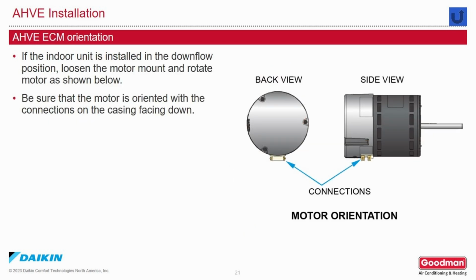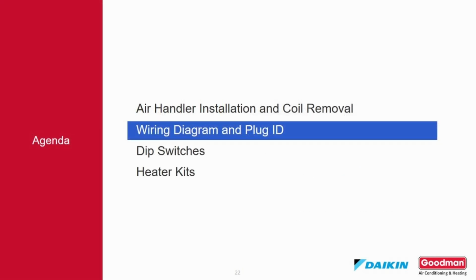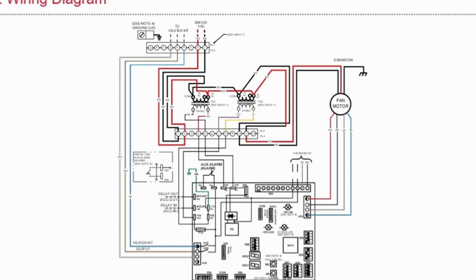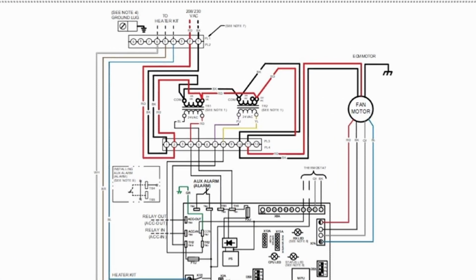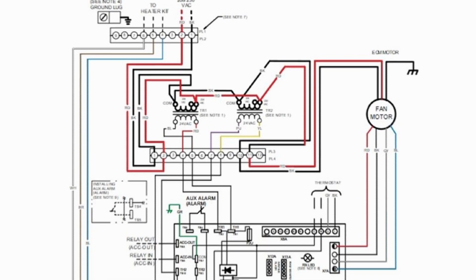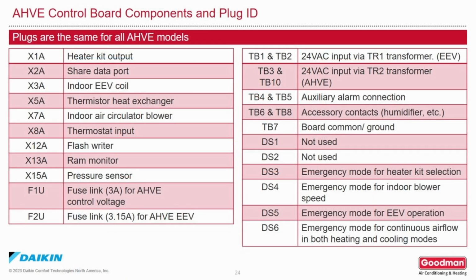AHVE ECM motor orientation. If the indoor unit is installed in a downflow position, loosen the motor mounts and rotate the motor as shown below. Make sure that the motor is oriented so the connections are facing downward. Wiring diagram and plug identification. Here is an AHVE wiring diagram. This can be found in the installation instructions or service manual. Plugs are the same on all AHVE models.